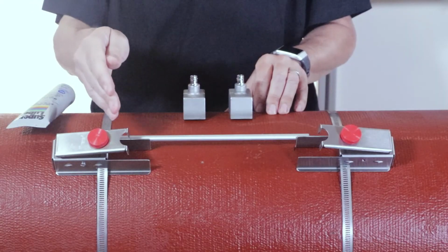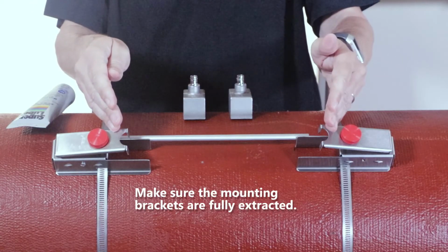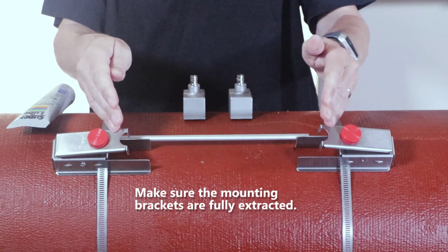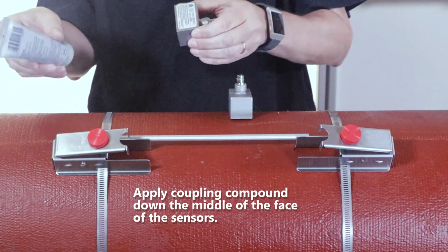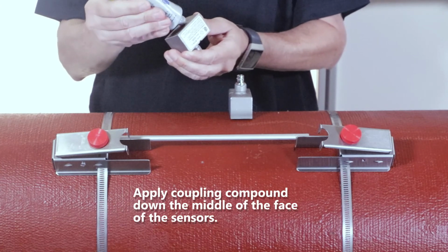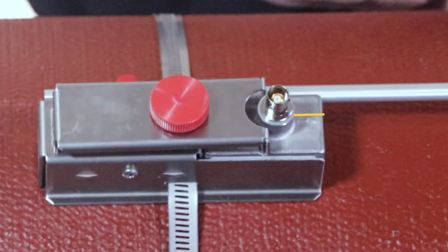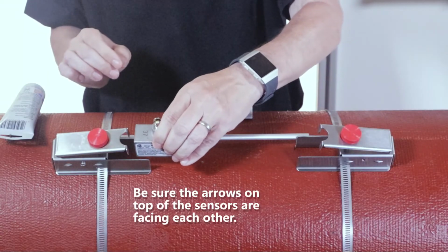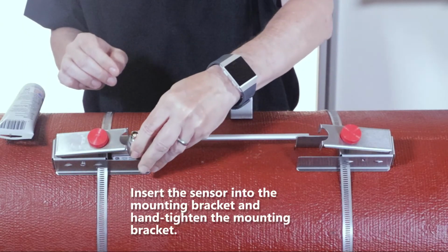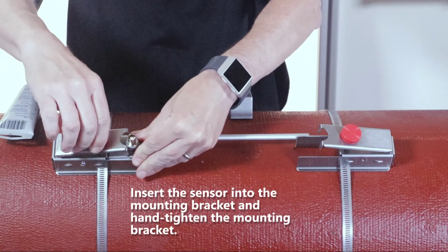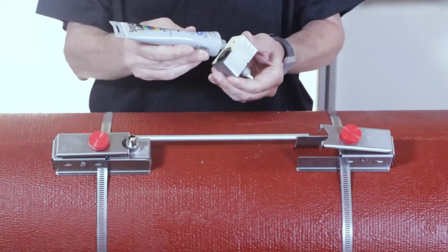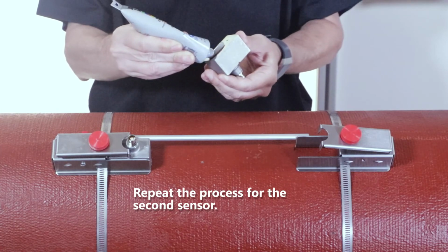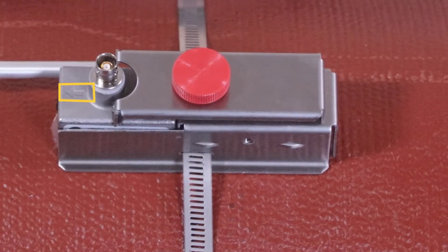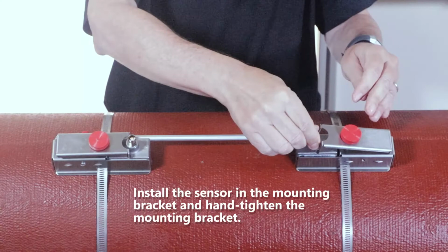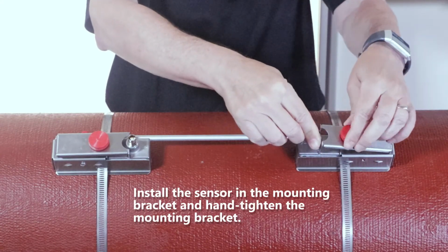It's now time to install the transducers. First, let's make sure that the mounting brackets are fully extracted. Next, we'll put coupling compound on each of the transducers. You'll see an arrow on top of each transducer. Make sure the arrows are pointing at each other, and then insert the transducer, hand tighten the mounting bracket. Repeat the process for the other transducer. Make sure the arrows are pointed at each other. Once the transducer is in the mounting bracket, hand tighten.